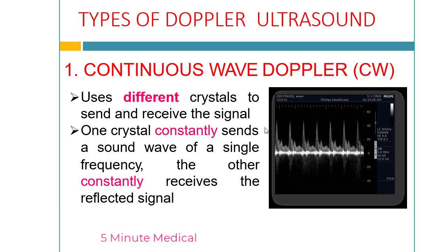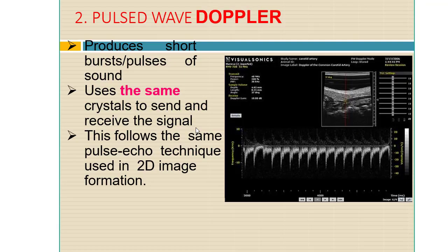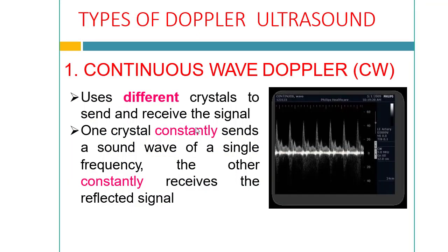In Doppler ultrasonography, one mode is continuous wave (CW) Doppler. CW mode uses different crystals to send and receive the signal. One crystal constantly sends a sound wave of a single frequency, while the other constantly receives the reflected signal.